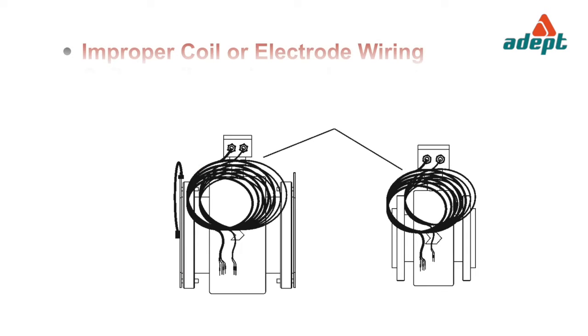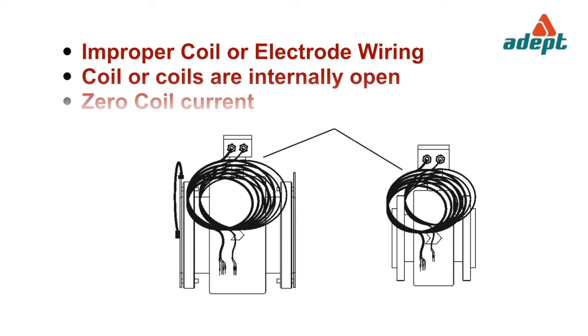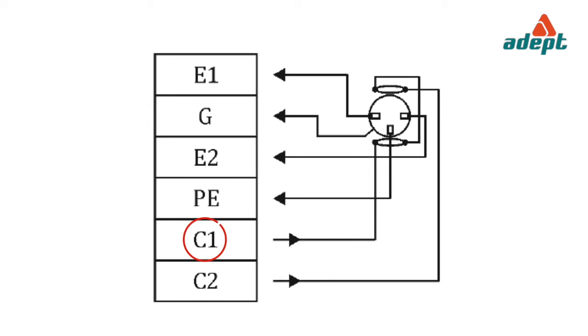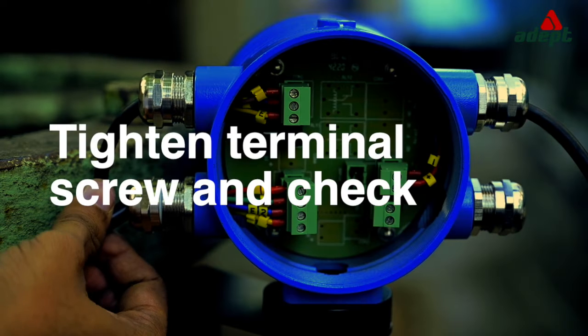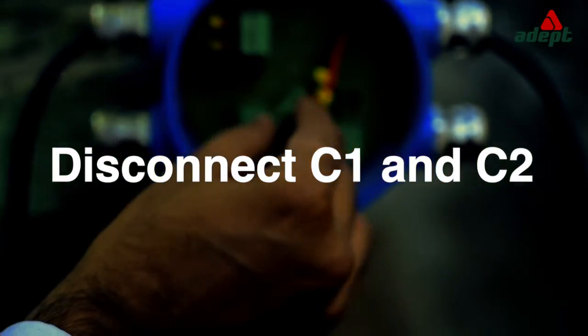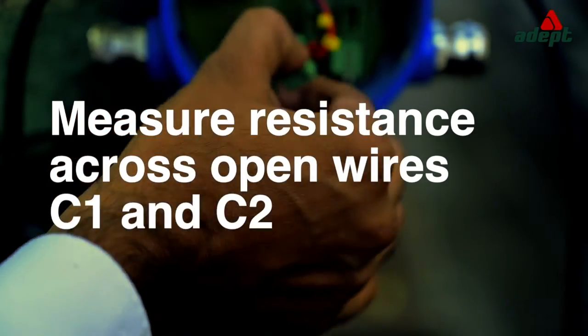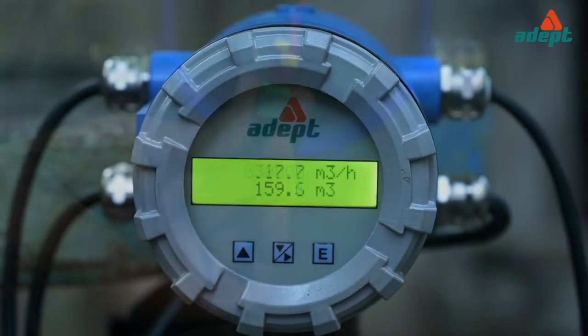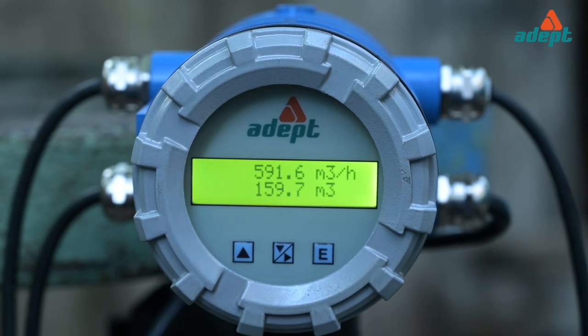Flow meter does not respond to change in flow. Possible causes: improper coil or electrode wiring, coil or coils are internally open, or zero coil current. Corrective actions: confirm that C1, C2, E1, E2, and G wires are correctly inserted into respective terminals at the transmitter and flow tube end, and tighten the terminal screws and check. Disconnect C1 and C2 at the transmitter; measure the resistance across open wires C1 and C2 — it should be within the specified range as mentioned in the manual.